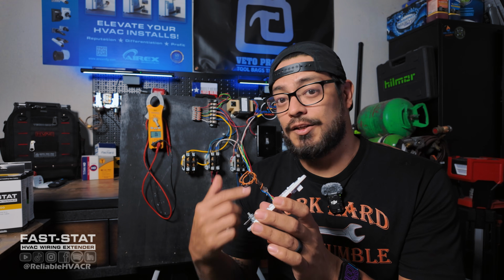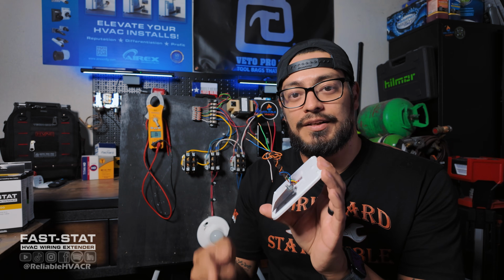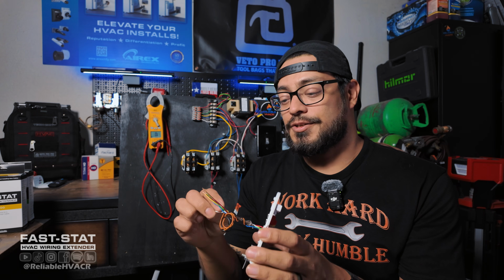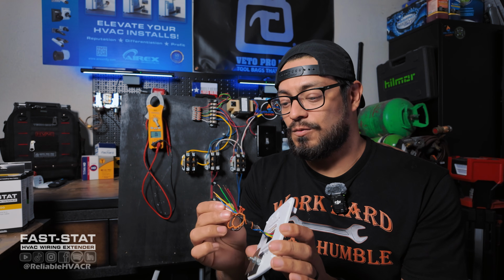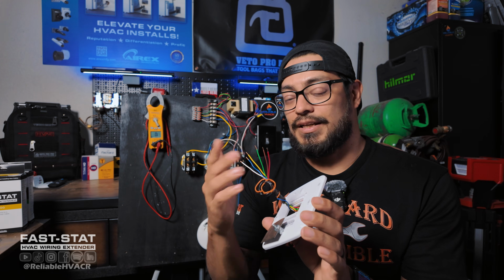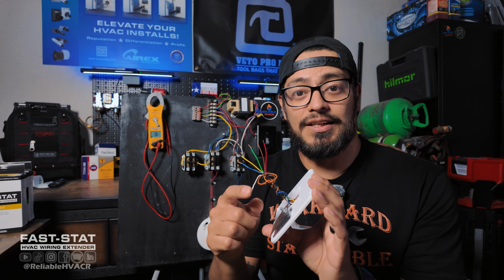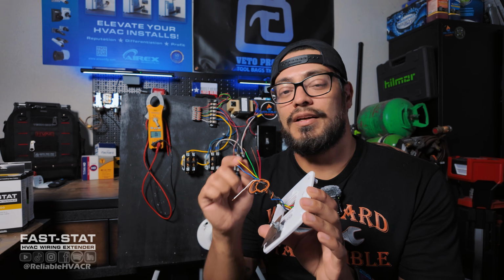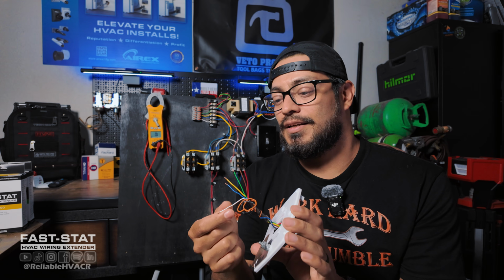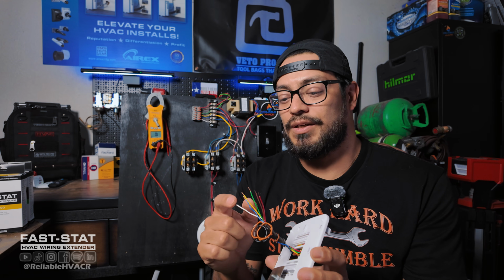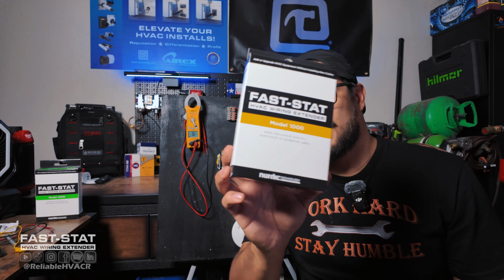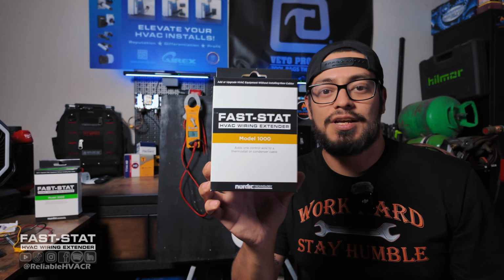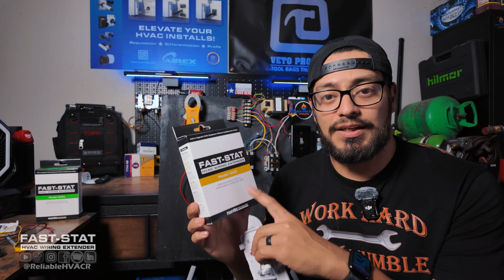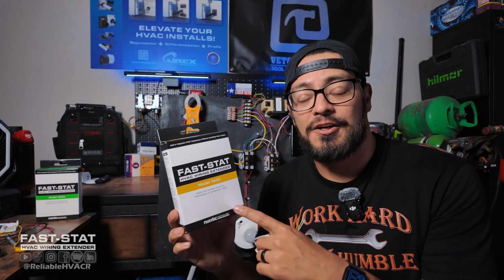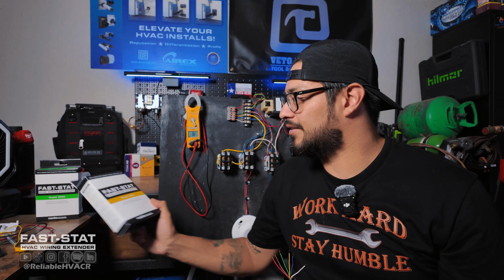You can just take another wire and condemn the one that doesn't work. You can also do that, like I said, for broken wires or shorted wires. Now, in an emergency, like I said, I'll take away the heating because we hardly ever use that here, and do the same process with that and land that over on cooling, whatever it is. But I mean, you can also use Fast-Stat. This one here gives you one extra wire to be able to use as a cooling, heating, whatever extra control wire you would need on this thermostat.